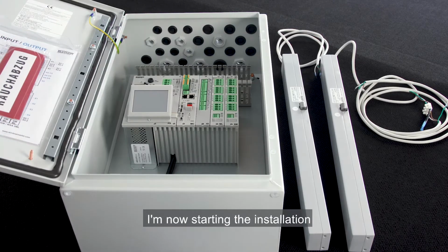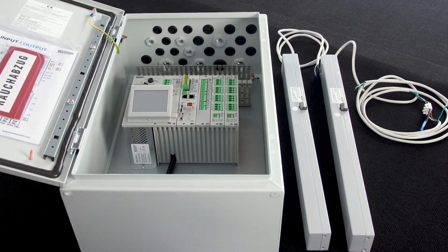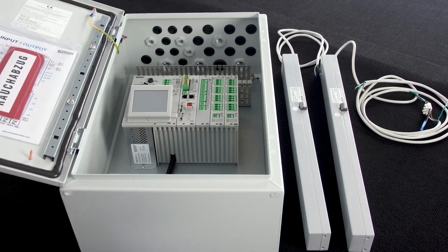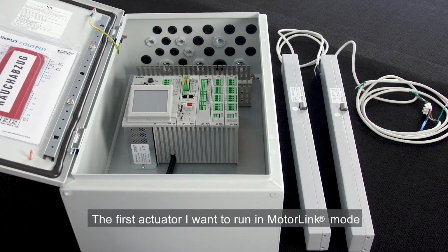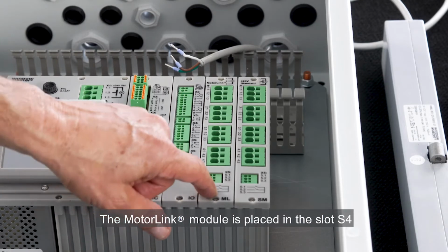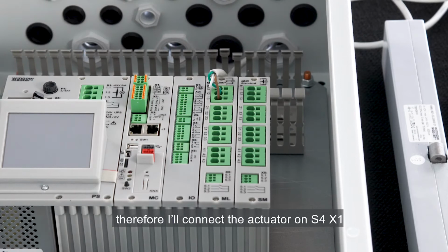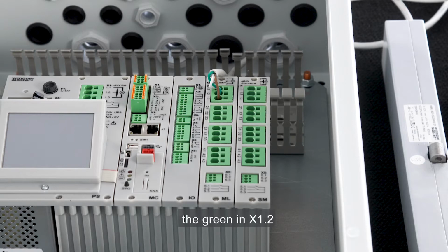I'm now starting the installation. The first thing to do is to connect the 2 actuators. The first actuator I want to run in MotorLink mode. The MotorLink module is placed in the slot S4, therefore I'll connect the actuator on S4X1, the white in X1-1, the green in X1-2, and the brown in X1-3.